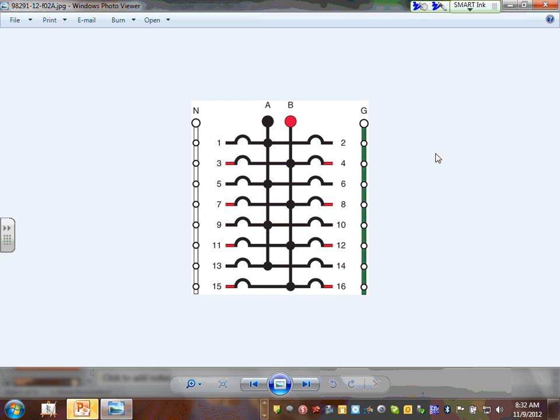If you're dealing with a single phase panel, I want you guys please to understand the following. From right to left, you're going to have phase A, phase B, or hot 1, hot 2. On the right side is going to be the neutral. On the left side is going to be the ground. Can I have thumbs up, Chad? You open this panel right now, you're going to have from left to right the phases A, B, and C, if any, and the neutral is going to be on the left. The ground is going to be on the right. If it's a service panel, they always bond the neutral to the ground.